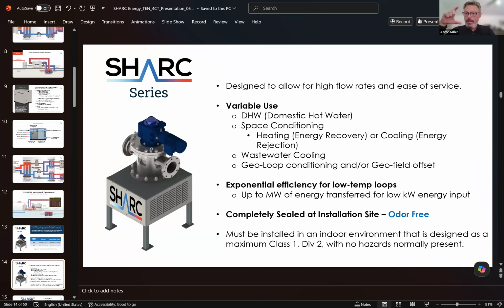You're only limited by the heat pumps that are connected to the clean side of our heat exchanger that are actually doing the work. What the SHARC is doing is taking the wastewater and filtering enough of it to make it into a state that you can use it essentially to power a heat pump. That's really all we're doing here, right? Instead of pulling water out of the ground, for instance, we're taking water from your sanitary line of your building or from the sewer in front of your street, and we're using that water just like we would in geothermal.